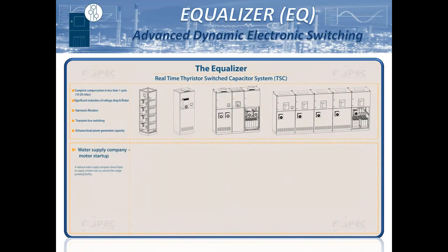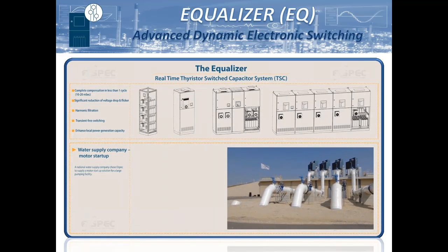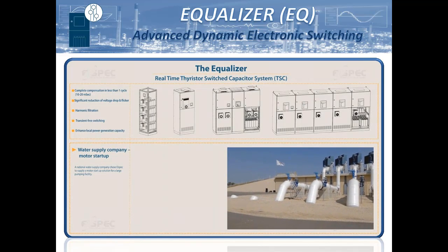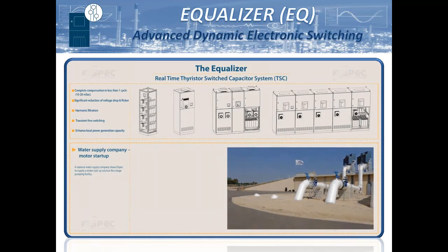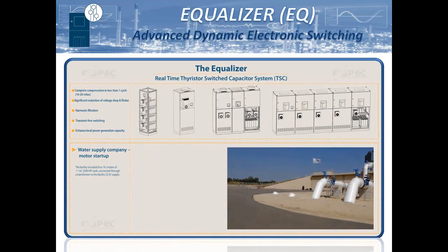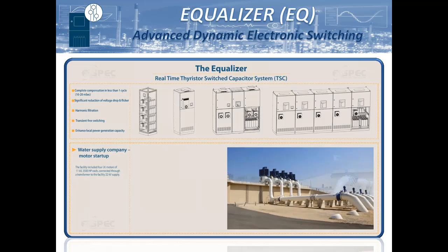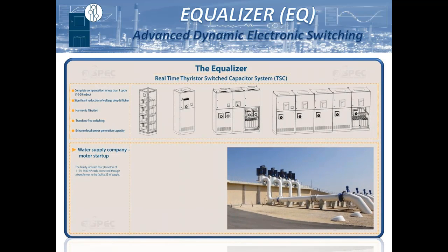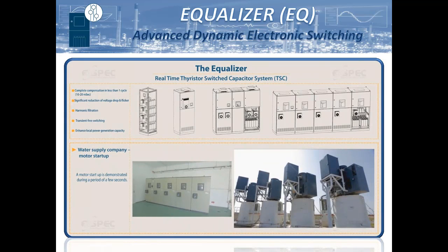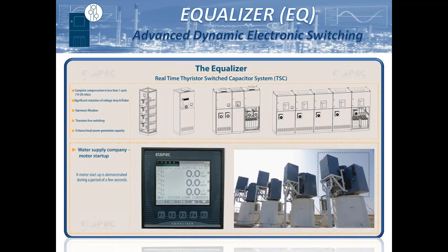A national water supply company chose ELSPEC to supply a motor startup solution for a large pumping facility. The facility included 4 motors of 11 kV, 3,500 HP each, connected through a transformer to the facility 22 kV supply. A motor startup is demonstrated during a period of a few seconds.